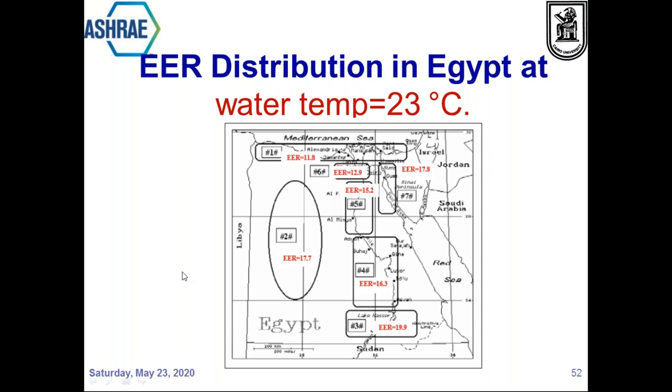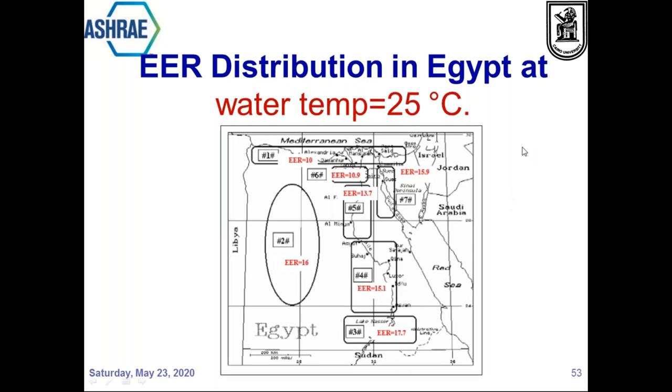So I'm just trying to walk you through the results. I'm not going to bore you with more experimental results, but once you get the test rig calibrated, tuned and running, you expect to get multiple good results that can mean a lot to the designer. Now let us go to 25. Still the EER is higher, but less than at 23 degrees centigrade spray water temperature.